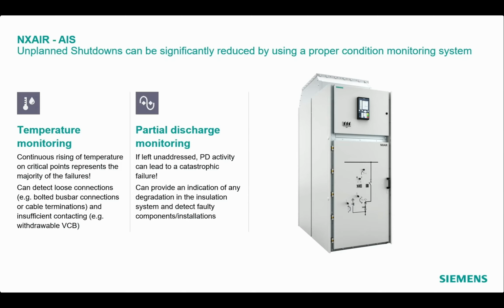The parameters to be monitored are principally the same as in the GIS, except the gas monitoring, which is not relevant in AIS. Therefore, we are monitoring temperature, as continuous rising of temperature on critical points represents the majority of the failures. Also, loose connections and insufficient contacting can be detected with the temperature monitoring. Partial discharge can lead to catastrophic failures, and therefore a monitoring can provide an early indication of any degradation in the insulation.